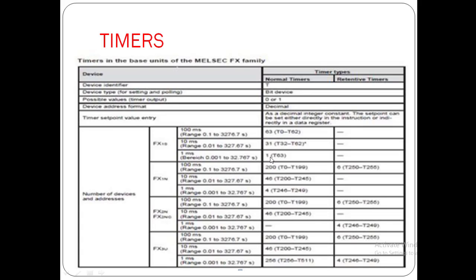In FX1S, the 10ms timers are 31, which are from T32 to T62. There is no retentive timer in FX1S — all timers are normal or non-retentive timers. In FX1N, you can have 200 timers of 100ms range, from T0 to T199 in normal condition, and the retentive timers are T250 to T255.